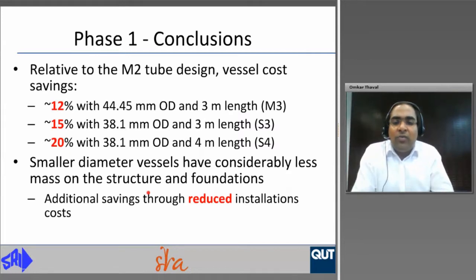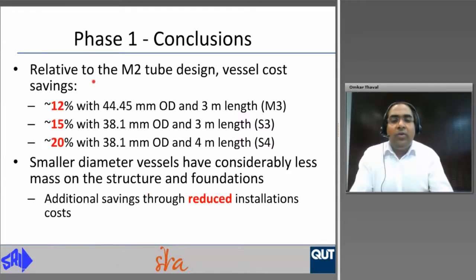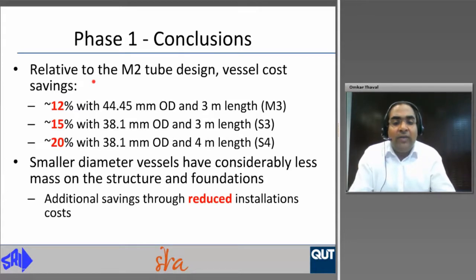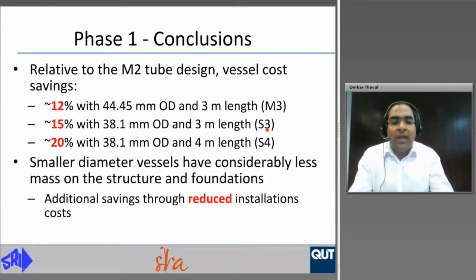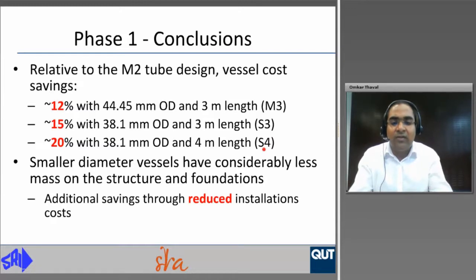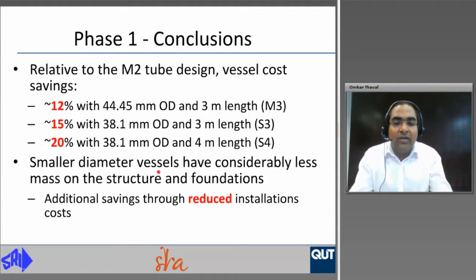In conclusion from phase one, relative to the M2 tube design, vessel cost savings can be 12% with 44.45 mm outside diameter and 3 meter length (M3), around 15% with 38.1 mm outside diameter 3 meter length, and around 20% with 38.1 mm outside diameter and 4 meter length (S4). These tube dimensions also have smaller vessel diameters, considerably less mass on structure and foundations, and additional savings through reduced installation cost.